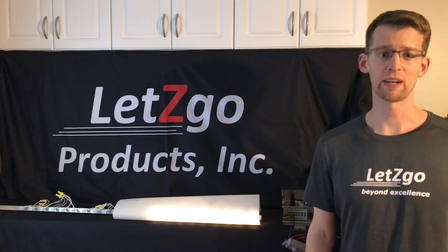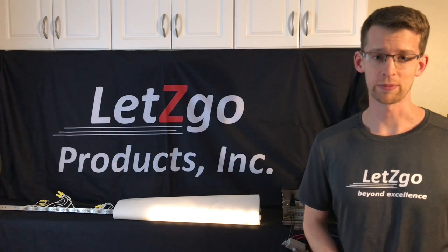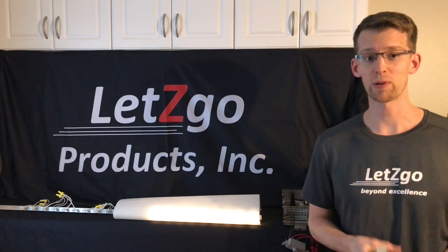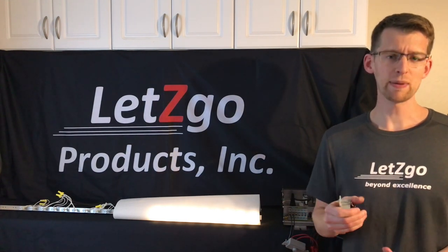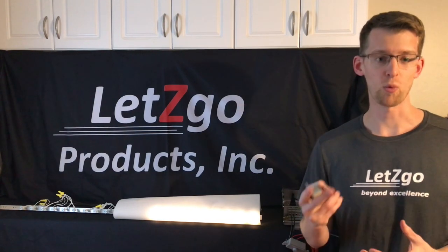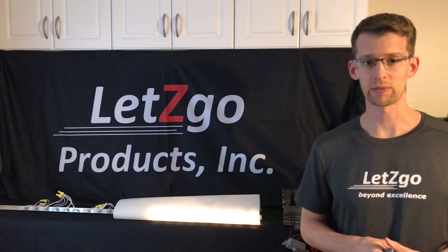Hi, I'm Matt with LetZgo Products. Today we're going to talk about dimming landscape lighting, and there are a couple of important things to get started. First, you need high quality dimmable lamps, and when I say dimmable, it needs to actually say on the lamp itself that it's dimmable. It needs to be high efficiency or high power factor, and you calculate your power factor by taking your wattage divided by your volt amp rating, which some manufacturers will post on their website.